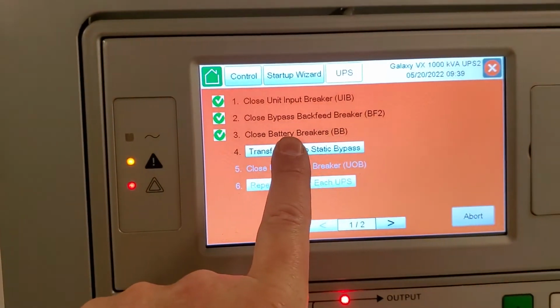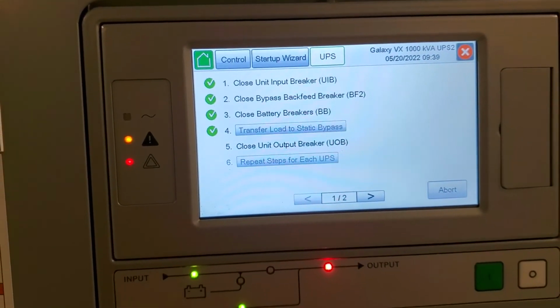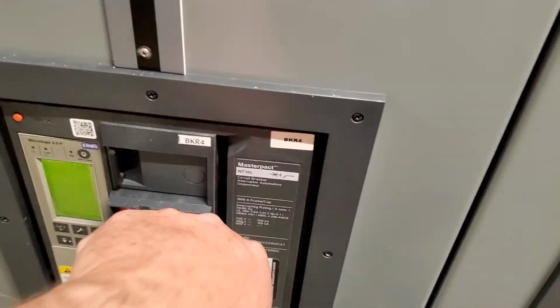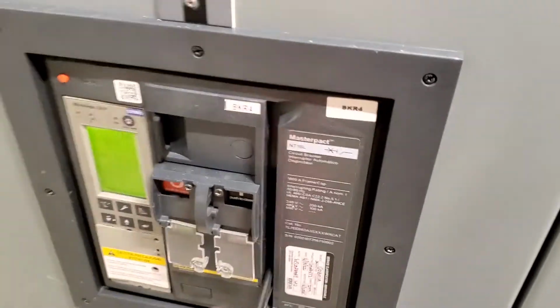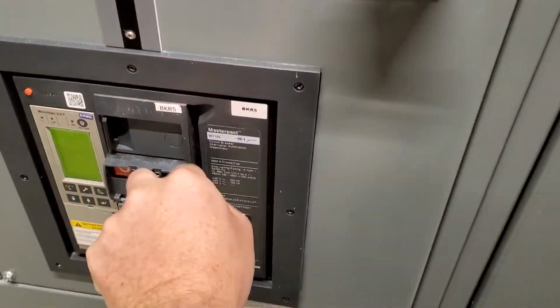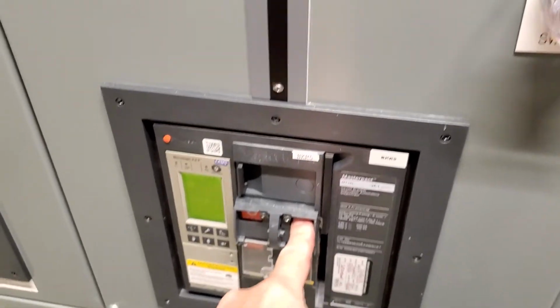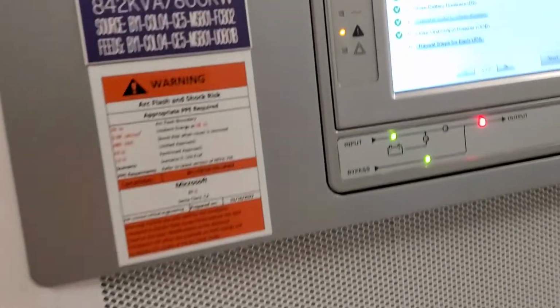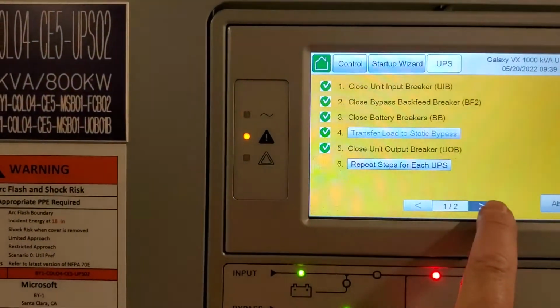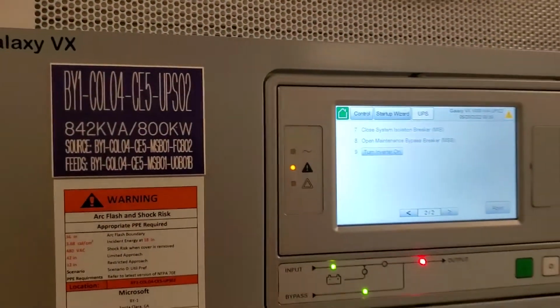Next, I have to move this to static bypass. As you can see, the bypass light has come on. I come over to the UOB breakers. I can close the UOB breakers, so I pump them up, charging up the spring on each one. And then I close both of them. Normally, if the UPS is not in maintenance bypass, then I do not have key release. So if we go over here right now, the next step is to close the MIB breaker, and to close the MIB breaker, I need the second Kirk key.